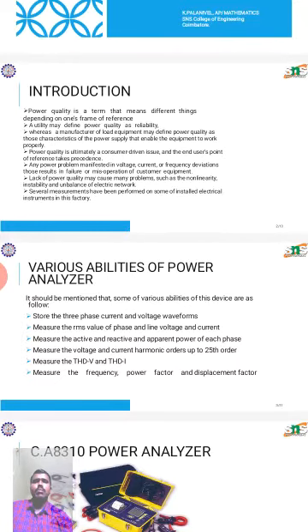cause many problems such as non-linearity, instability and unbalance of the electric network. Also, power quality problems will decrease the lifetime of electrical instrumentation. In this case study, the effects of harmonic distortion on the performance of transformers, cables and induction motors have been studied, and the complex series form of Fourier series is also considered. Then, after the theoretical study, harmonic and complex power quality indices of several devices have been measured.